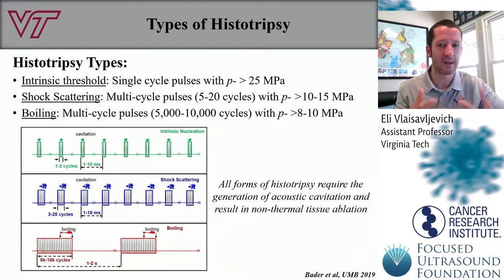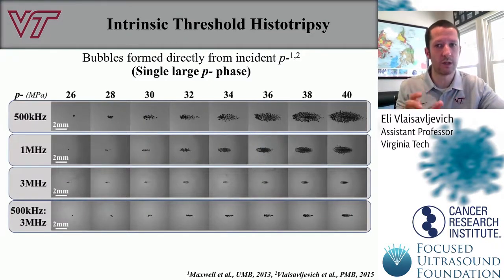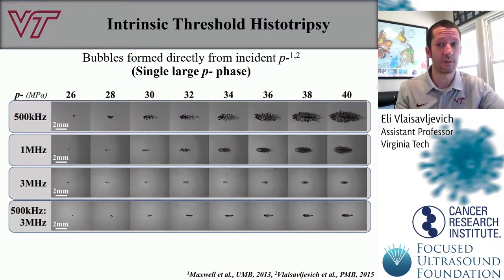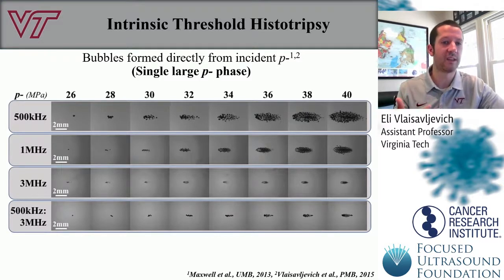It's a non-thermal mechanical effect generated from bubbles formed at the focus of the transducer. In intrinsic threshold histotripsy — also referred to as microtripsy in the literature — these single cycle pulses are used to generate a precise and dense cavitation bubble cloud that can be tailored based on the acoustic parameters. This gives us high precision, so we can match the size of this bubble cloud as well as other properties to selectively tailor treatments for different targets of interest.